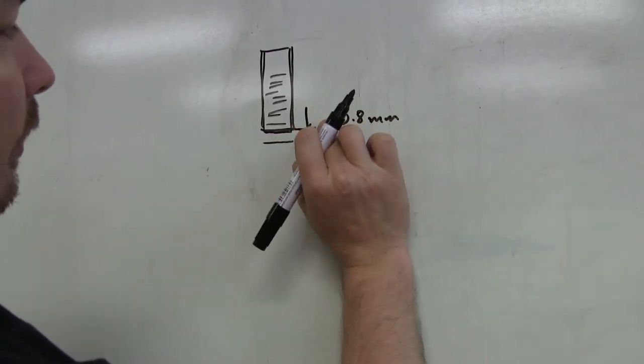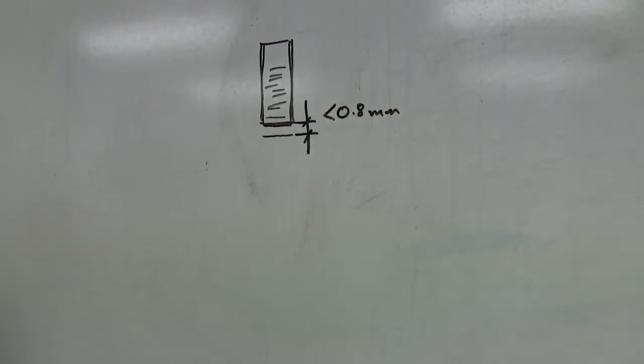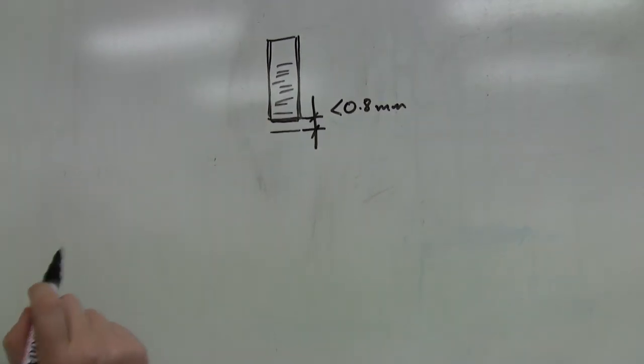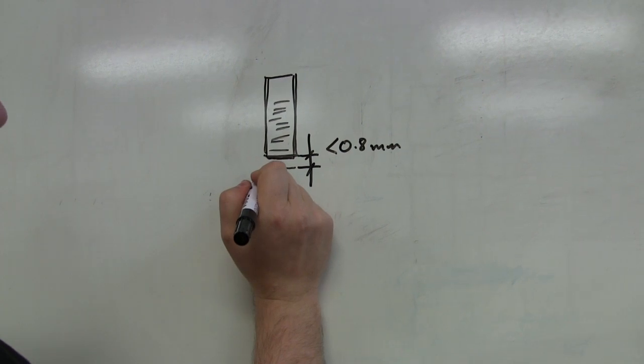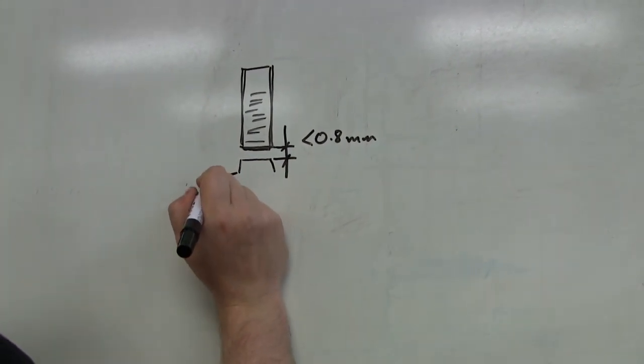The gap between the sensor and the surface it's measuring should be 0.8 mm or less. Now, we've set this up in the next room, and we'll see that in a second. Now, ideally, what you usually use it for is to measure gear teeth.